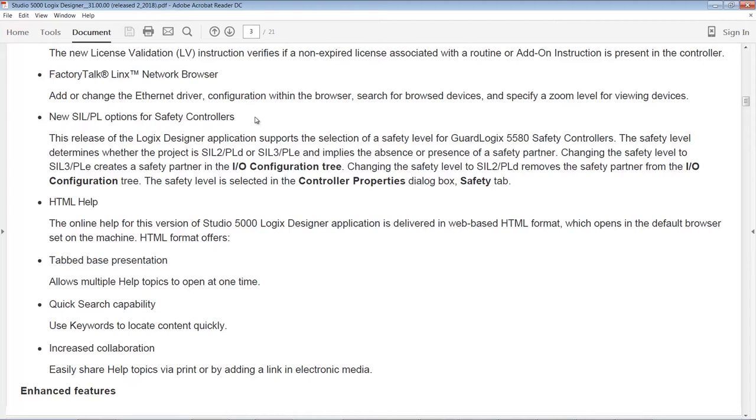New SIL and PL options for safety controllers. We talked about this late last year where they were allowing the ability to use either a safety controller by itself or a safety controller with a partner to enable SIL 2 or SIL 3, or PLd versus PLe. What we're getting here with these new SIL/PL options is if you select SIL 2, you don't have to have a safety partner and the safety partner would be removed from the IO tree. If you choose SIL 3, automatically added to the IO tree will be the safety partner and that will be required in your project. So that's pretty cool.